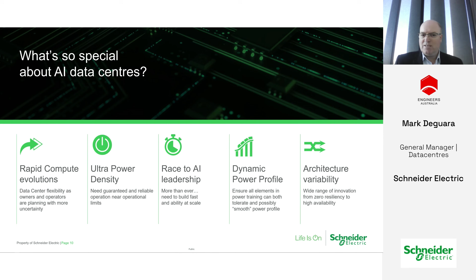Last, but certainly not least, is architecture variability. This is probably the biggest challenge facing the industry today - the ever-changing dynamic. Not so much from the core external infrastructure - if I look at the MV feeding the site, other than the larger capacity 400 megawatt data centers, it's really impacting the white space. What's happening at the rack? How do I get cooling to that rack? How do I get power to that rack? And how do I reticulate power - is it AC fed, is it DC fed, is it liquid cooling, is it air cooling?